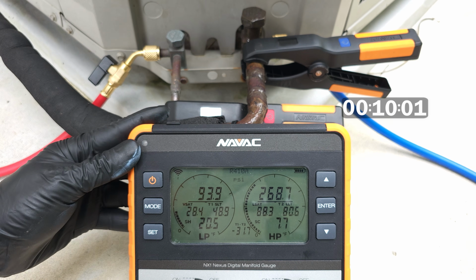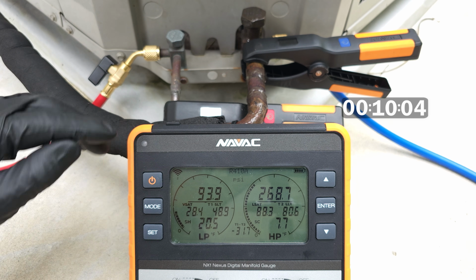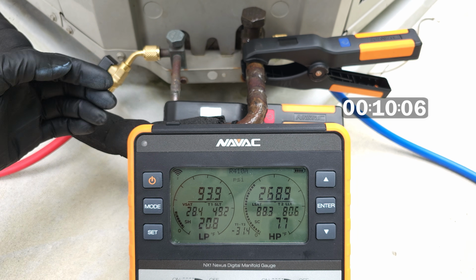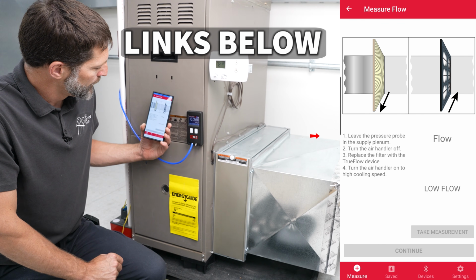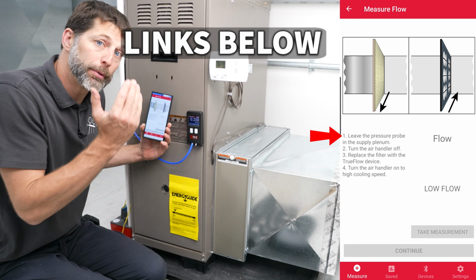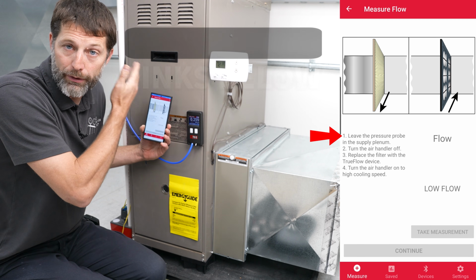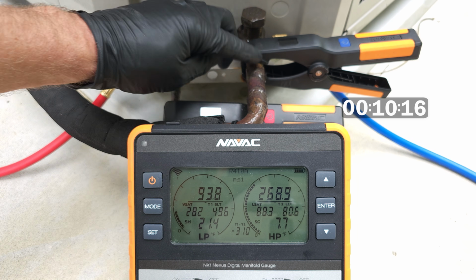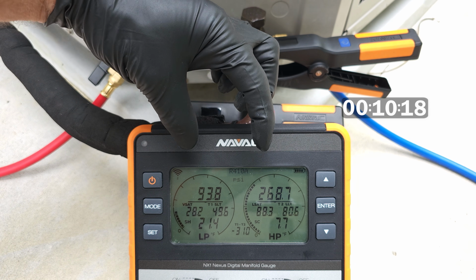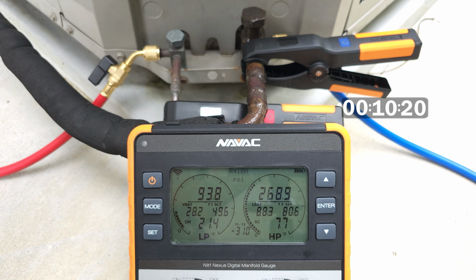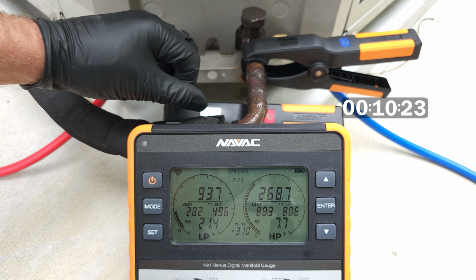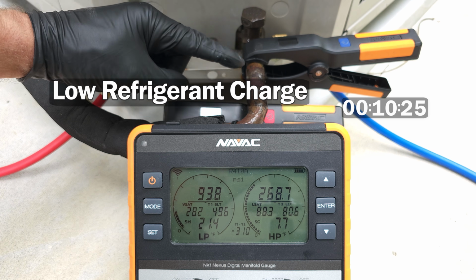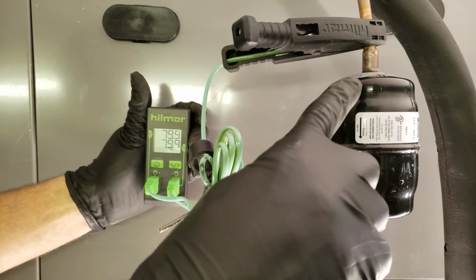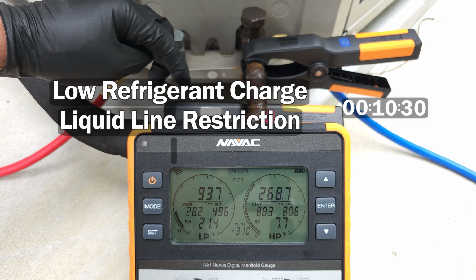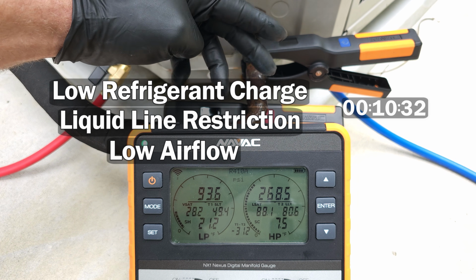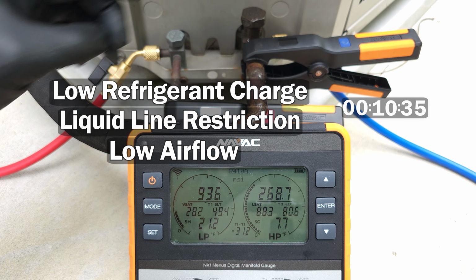So of course, I chose to do this backwards just to show you in this video. In other videos, you can see how to measure the airflow, and I'll actually show you what our CFM measurement is inside the building here. But you can determine why this suction line is frozen with your refrigerant indicators here. If this is frozen, it's either one of three things. It's either low refrigerant charge, a liquid line restriction like a clogged filter dryer, a bad TXV like it's clogged or something like that, or you have low airflow. A lot of times you have low airflow as the problem.